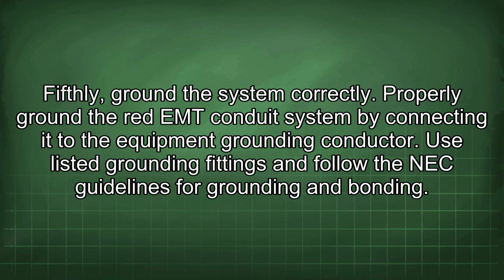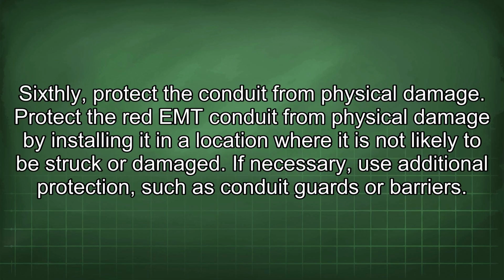Fifthly, ground the system correctly. Properly ground the red EMT conduit system by connecting it to the equipment grounding conductor. Use listed grounding fittings and follow the NEC guidelines for grounding and bonding. Sixthly, protect the conduit from physical damage. Protect the red EMT conduit from physical damage by installing it in a location where it is not likely to be struck or damaged. If necessary, use additional protection such as conduit guards or barriers.